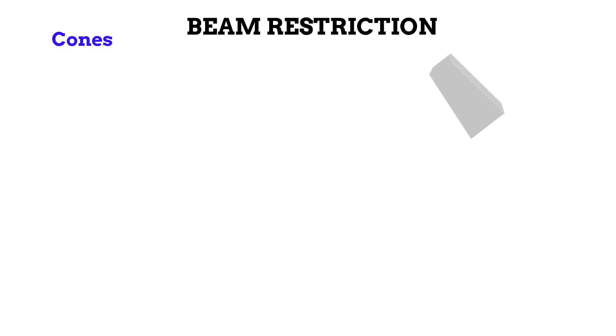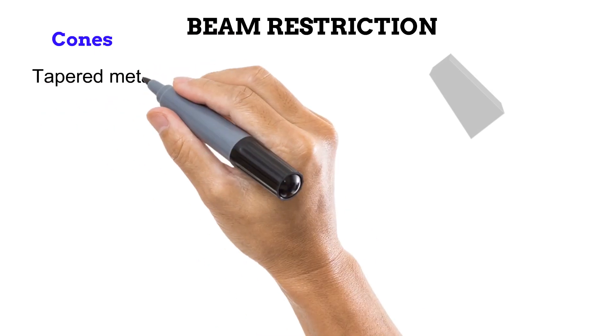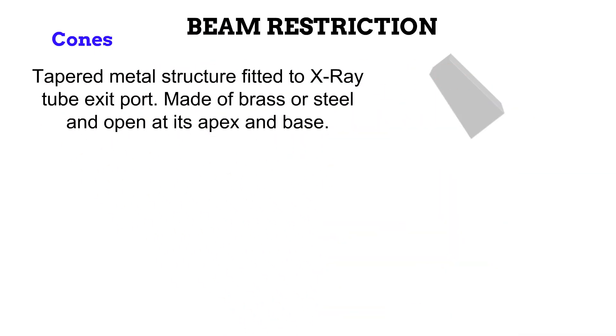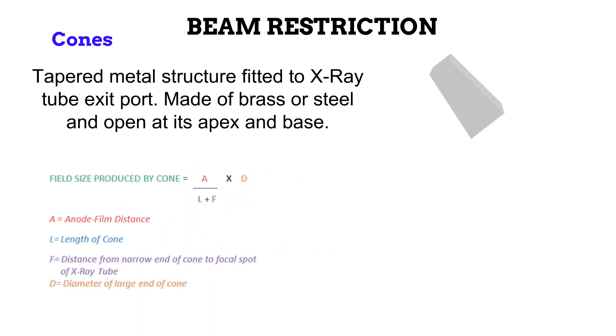Next is the cone. This is also fitted to the exit port of the X-ray tube like the aperture diaphragm. It however differs in that it is not a flat metal sheet — it is a cone-shaped tapered structure that increases from its apex to its base. It is made of brass or steel, and is open at its apex and base. It is through these openings that the X-ray beam is shaped into a much narrower form. The width of the field produced by a cone can be estimated using the formula: Field size equals A divided by (L plus F), all multiplied by D — where A is the distance between the anode and the image receptor, L is the length of the cone, F is the distance between the narrow end of the cone and the focal spot of the tube, and D is the diameter of the wide end of the cone.